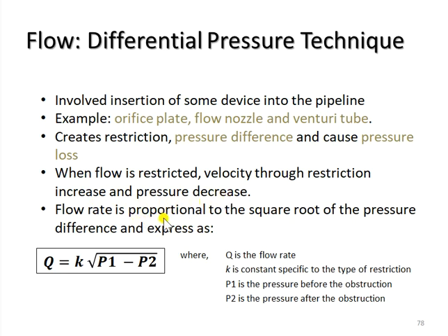The flow rate is proportional to the square root of the pressure difference and can be expressed as the following equation. The flow rate, Q, is given by the square root of P1 minus P2, and multiplied with a constant of the restriction, k. P1 and P2 are the pressure before and after the obstruction, respectively.